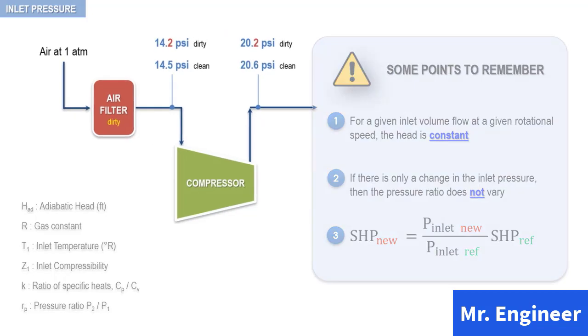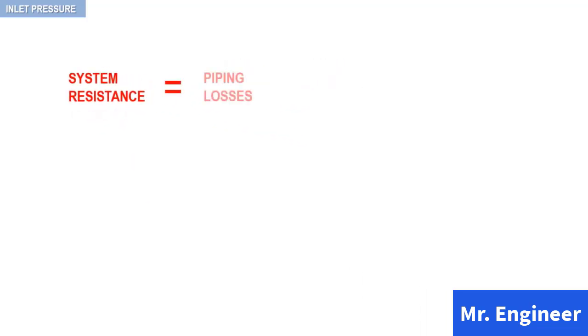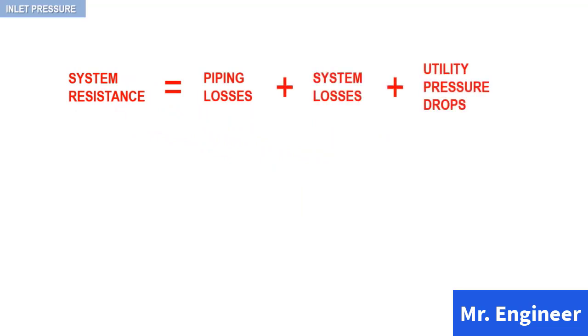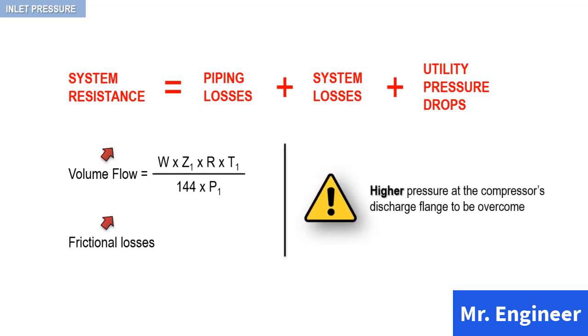In this example, we have ignored the effects of system resistance downstream of the compressor discharge flange. For many applications, system resistance is small compared to the total pressure requirements of the compressor and will therefore have minimal effect on the analysis. In some applications, however, system resistance effects are large and will actually define the compressor operation. We can view system resistance as the sum of piping and system losses and utility pressure drops. As the volume flow through the system increases, frictional losses increase and require a higher pressure at the discharge of the compressor to be overcome.